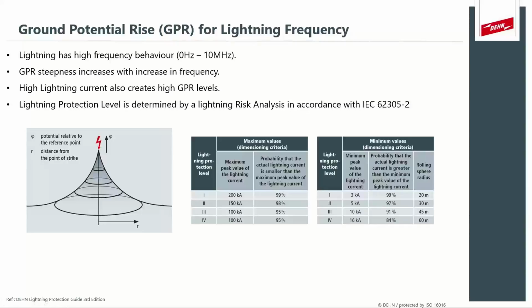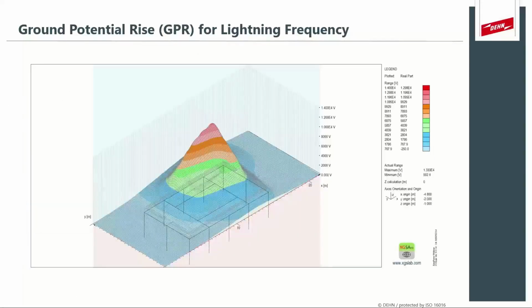Now, if we took the same situation we had previously of our grounding grid that was poorly designed, in that case, I injected 360 amps of fault current into the grid. If we use the same fault current of 360 amps, but I just change the frequency to a representative frequency of 250 kilohertz for first negative, we can see already that the equipotential plane is completely gone, purely based on the frequency and not even the actual fault current.